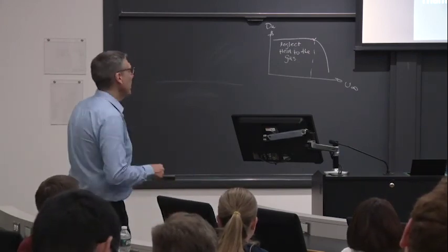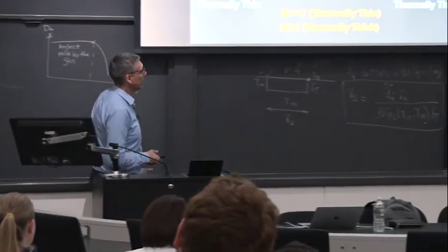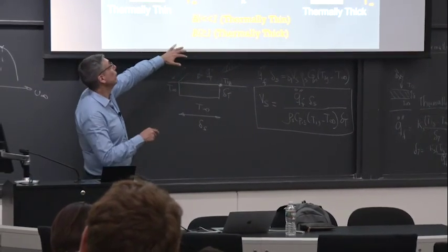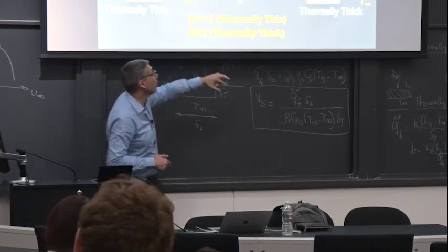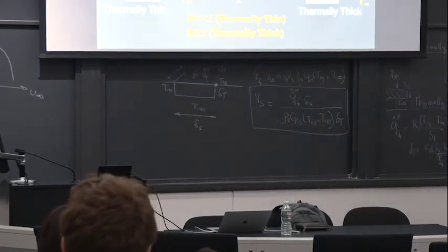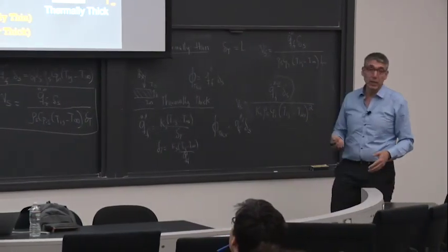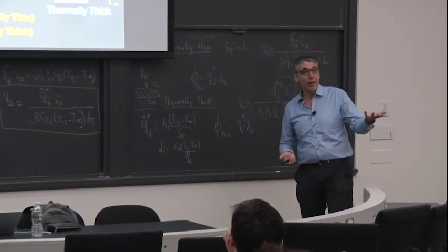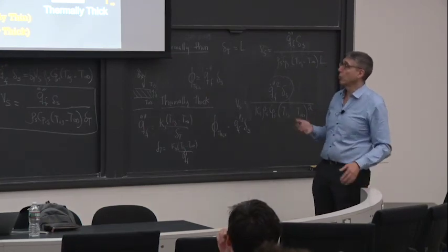Now, of course, many people will argue, where do fire materials end? Well, the majority are thermally thick. So even if you have a very rough idea of your heat transfer coefficient or your film coefficient, you still will always land with a value that is much greater than one, okay? Very rare you get thermally thin materials, and generally it's quite obvious. I mean, it will be paper, that type of material, fabrics. You know, very, very thin materials that effectively allow you to operate like that.